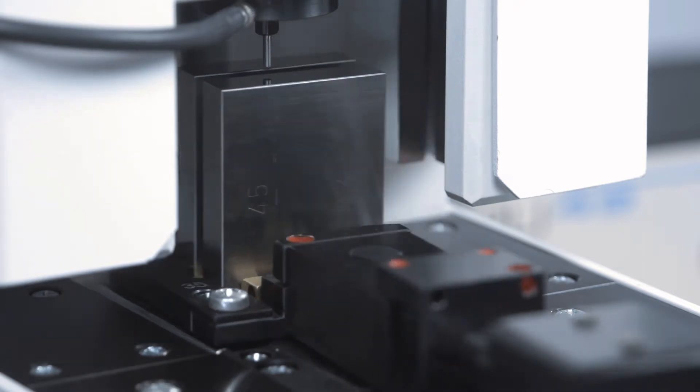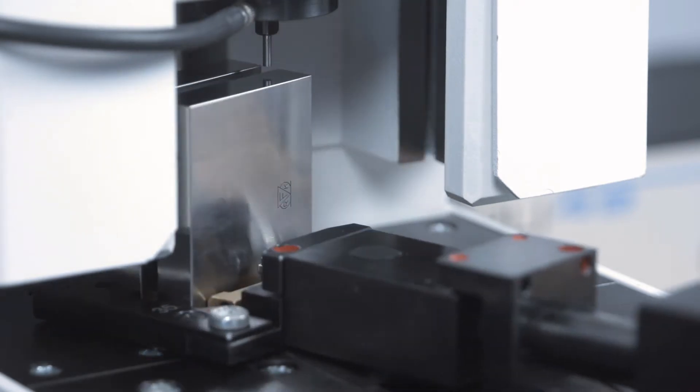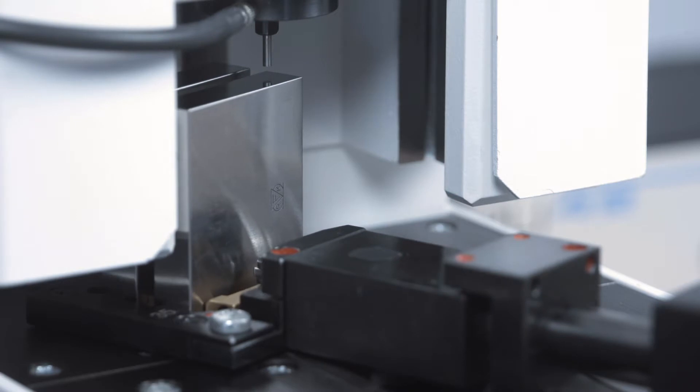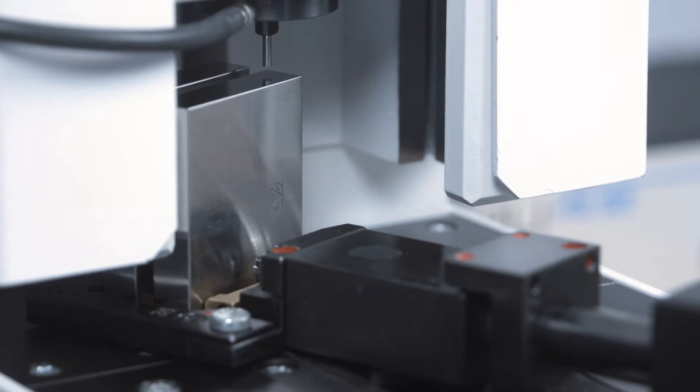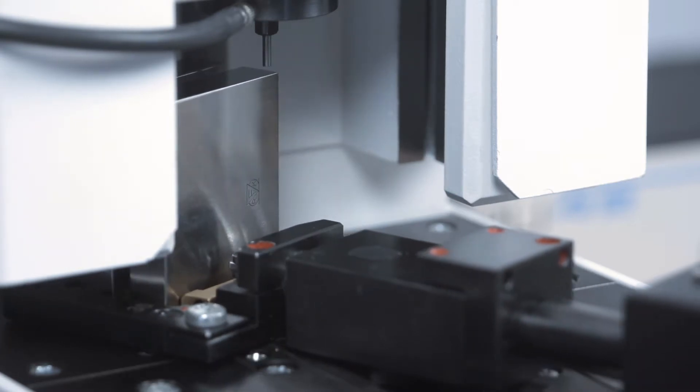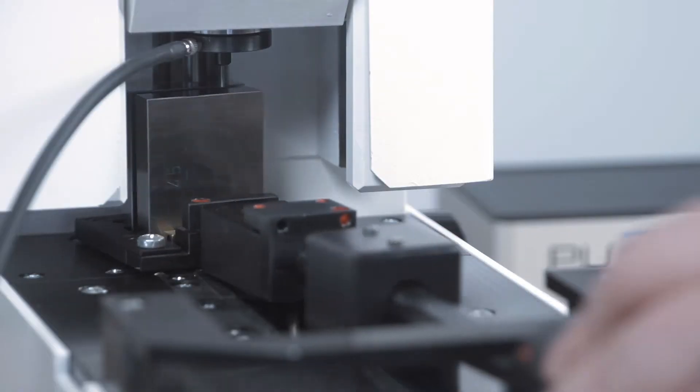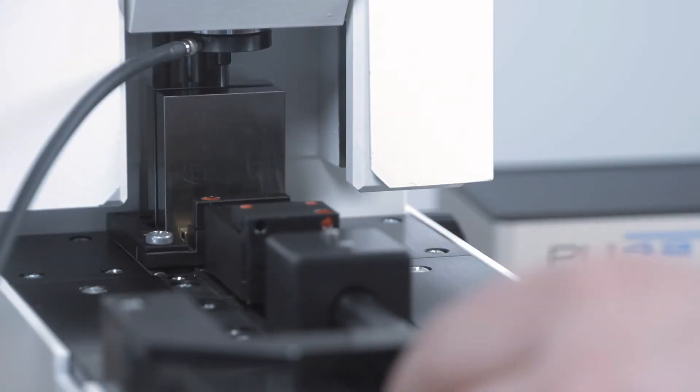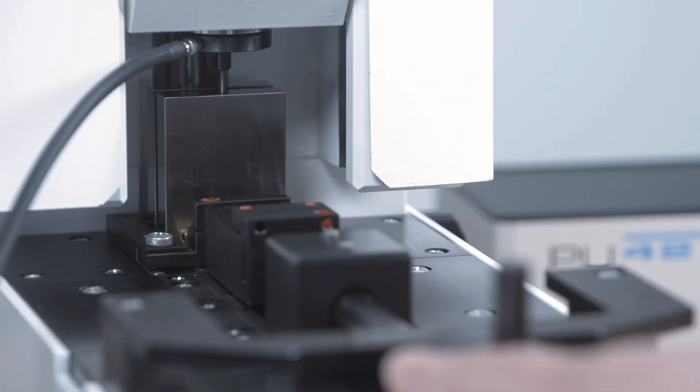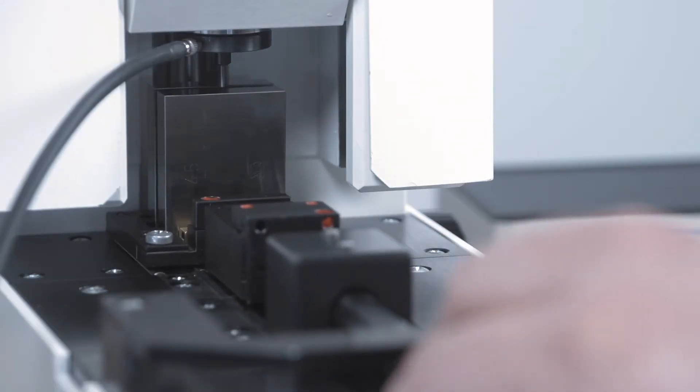The detent plate ensures a very fast and accurate positioning on the reference gauge block and the five measuring points on the test gauge block. All of this takes place in next to no time.